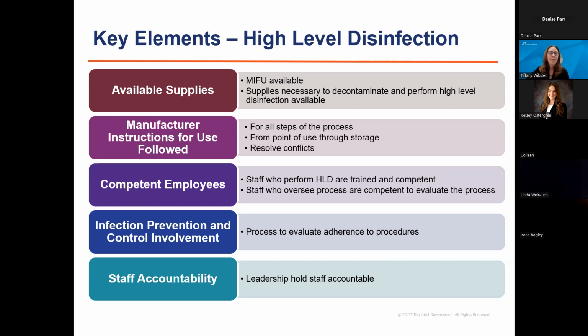So when you think about manufacturer's instructions for use being followed, think about the most complex thing I can think of, which is an endoscope, right? There are a significant number of brushes and flushes. And if you flush before you brush and you don't flush after you brush, you could be leaving debris in the channels. So making sure that all of the steps of the process are performed correctly in the right sequence is really, really important.